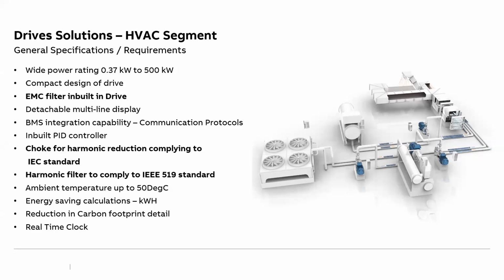Then basically EMC filter and harmonic filter. So apart from the benefits of the VFD, there are certain problems also associated which we need to take care of. For example, EMC. EMC is a disturbance or a noise which is caused by the VFD, and we need to protect against it. There are some filters available, so we should ensure that this VFD has the inbuilt EMC filter. We'll see in a little more detail after this what EMC and harmonics are. So it should have the EMC filter as well as the basic harmonic filters inbuilt.